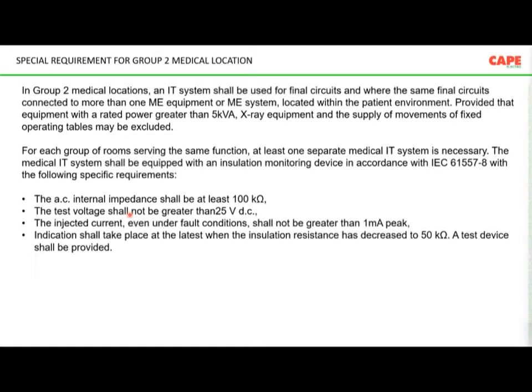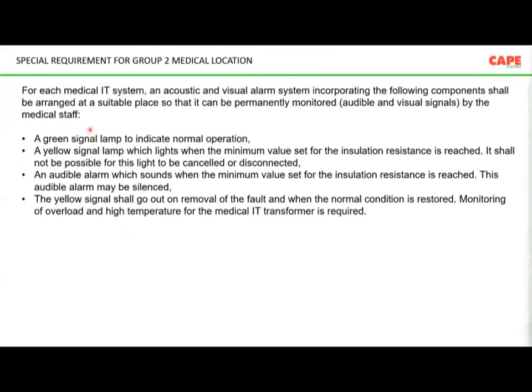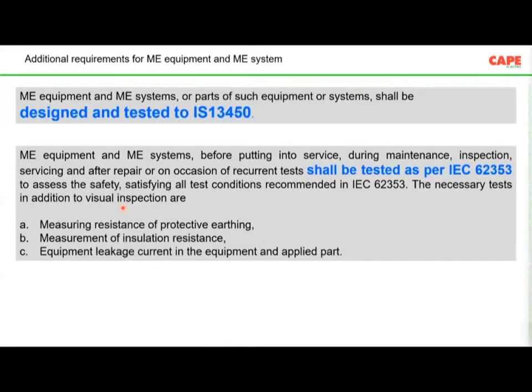What we will do extra is make a blog on our website, and the blog will also be shared with you. As a result, you will be able to understand and download all these documents. So here, for the medical IT system, the internal AC impedance, the test voltage, and all these requirements are given. Then again, for medical IT, in case of a single fault, what you should do, or in case of any insulation resistance reduction, what is necessary is also very well documented.